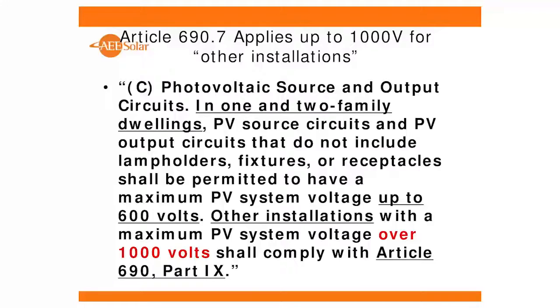Because the way it was set up is that low voltage was 600 volts and below, and then medium voltage started at 600 volts and went up to whatever, tens of thousands of volts. And so you have all these requirements that are based on medium voltage that are being applied to an 800 volt system. Well, particularly for PV, that was a problem, and so this basically changed it to say that 1,000 volts or less, essentially, if it's not a 1 or 2 family dwelling. So it kept 600 volts or less for 1 and 2 family dwellings. And why did we do that?